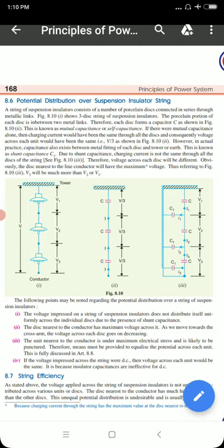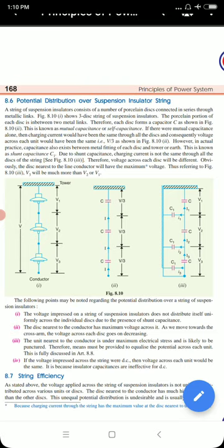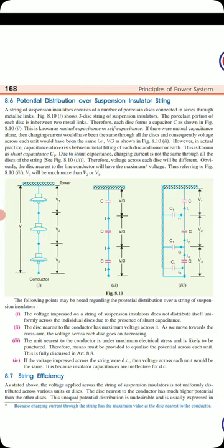The total voltage across the three insulators is V. Ideally, since each disk is of the same size and same dielectric strength, the voltage should distribute equally — so V1, V2, V3 would each be V/3. The capacitance of each disk is C, called self capacitance or mutual capacitance, and the voltage across each disk would be V/3.